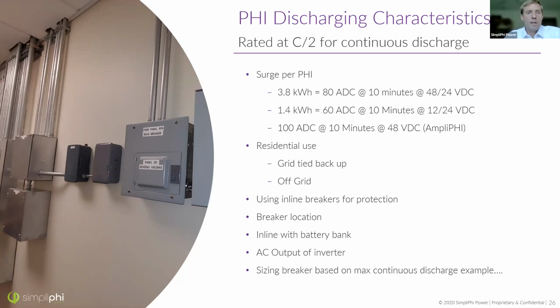Okay, so these batteries should be sized, and we're going to get into sizing a little bit. For residential use, we typically are seeing these in grid-tied backup. You can either have grid-tied, you can even have off-grid with these, of course. And so there are considerations that go into each of those. Of course, for both grid-tied and off-grid, you want to make sure that your inverter is not drawing power out of your batteries any faster than this. So for each battery, not looking at the surge, under normal conditions, you're getting about 1.9 kilowatts from our Phi batteries. So if you have a 6 kilowatt inverter, you're going to want to have 4 batteries to run that 6 kilowatt inverter.